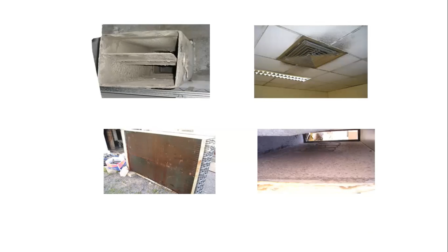You also have to understand the location of the fresh air unit, because sometimes there's an exhaust nearby with a fresh air intake close to it. So the air current can carry smell and dust particles back into the air handling unit room. You have to see all this when going to the actual design - this is just for guidance purposes.